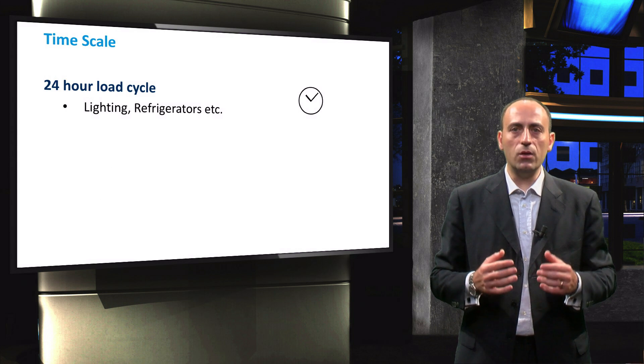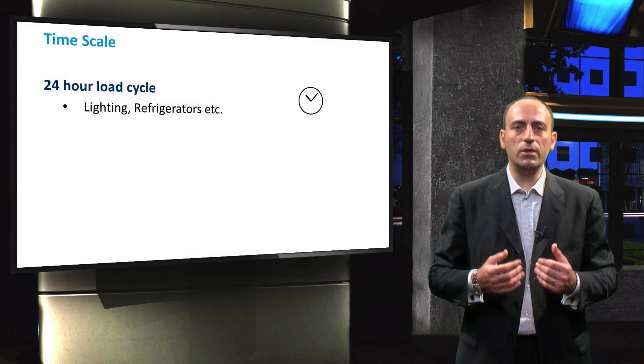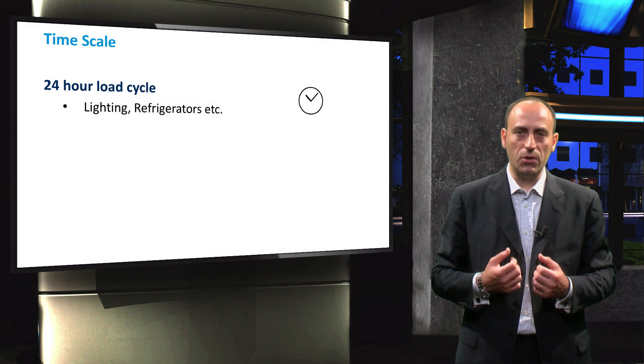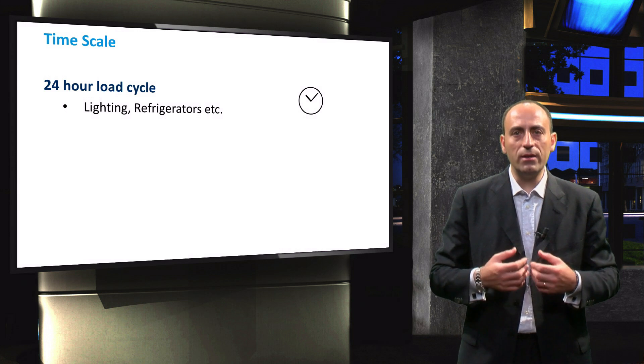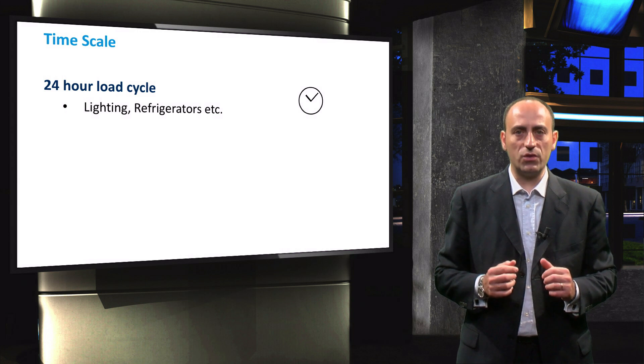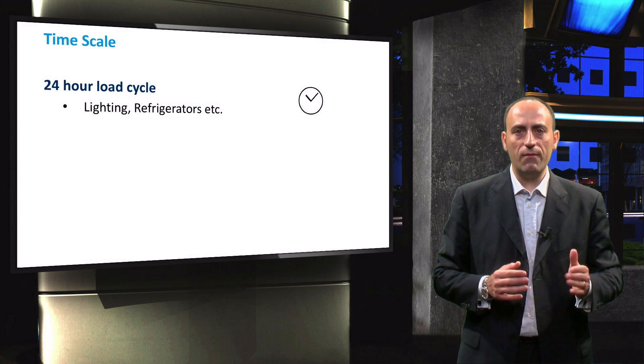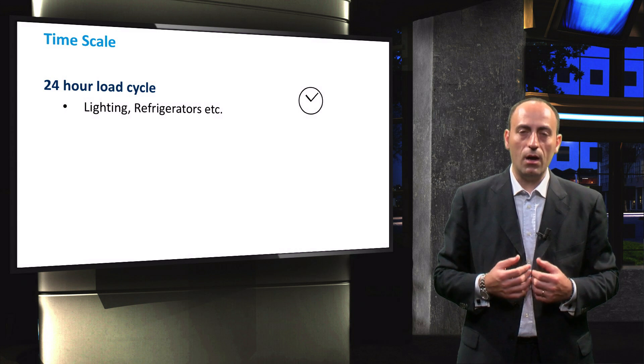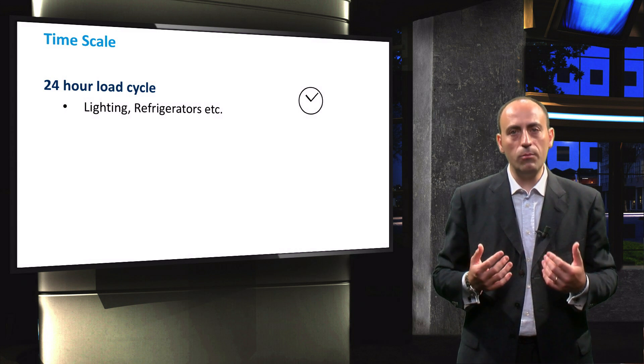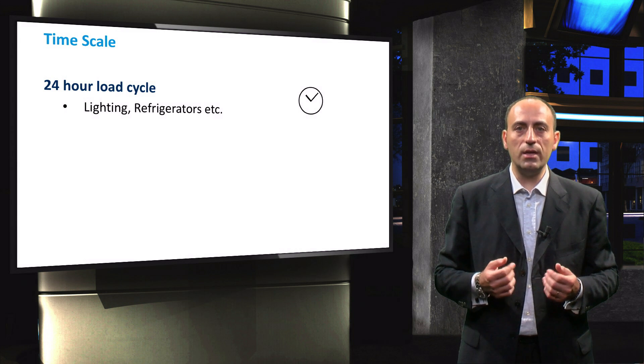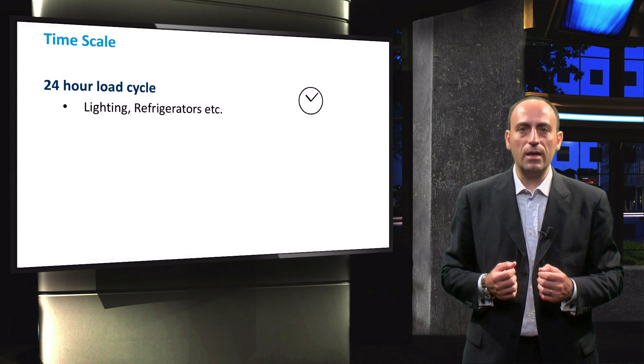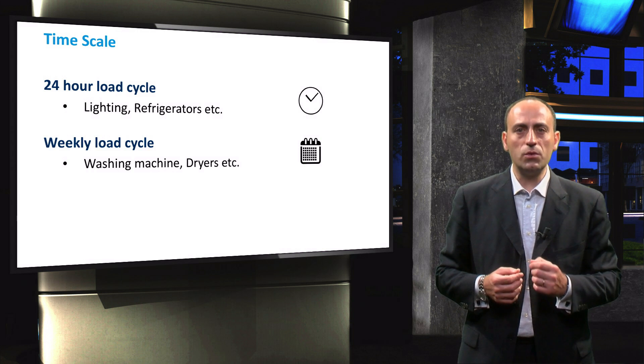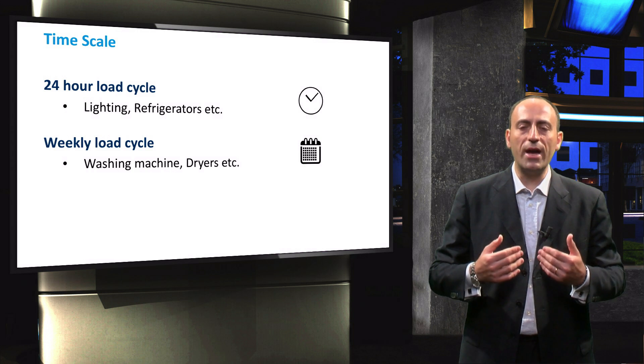In PV system design, load profile analysis will often depend on the available resources. Analysing a load profile can be performed with increasing complexity and accuracy. The simplest model is to determine the load profile of a 24-hour load cycle and assume the load profile is the same every day. However, such analysis might not include all loads, as it might not take into account loads that are not operated every day — typical examples being the washing machine and the dryer. When such loads are present, a weekly load analysis will give a more accurate result.